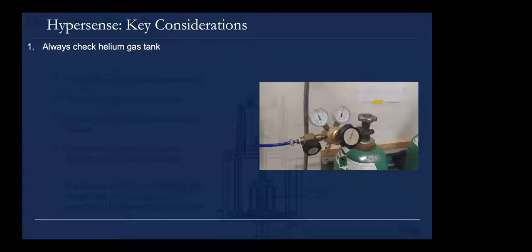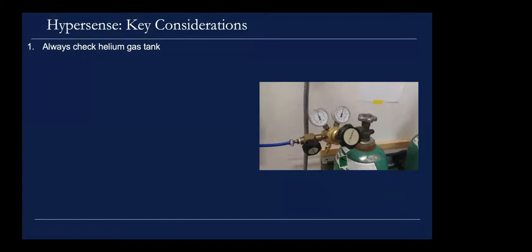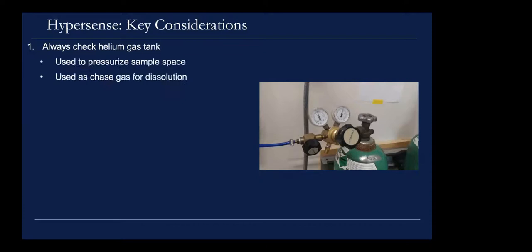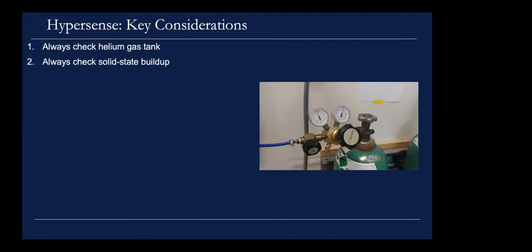A few things to keep in mind when running these experiments: always check the helium gas tank. It's used to pressurize the sample space and as chase gas to clear lines after dissolution. If you don't have sufficient helium gas, you won't be able to run the experiment; without positive pressure in the sample space, you'll pull air in, it'll freeze inside the insert, and the system will be down for days. Always also check your solid-state build-up — it's a quick sanity check and a good metric to monitor.